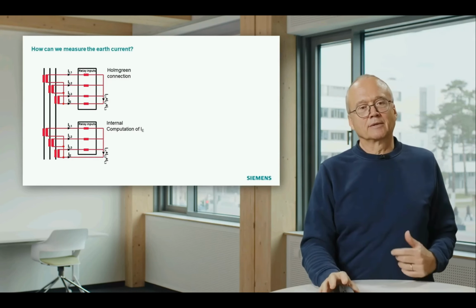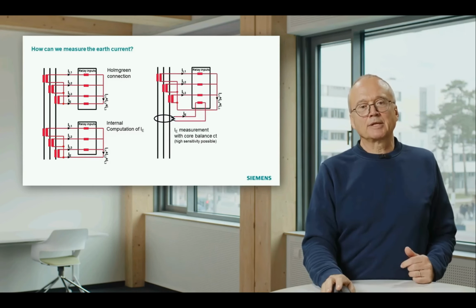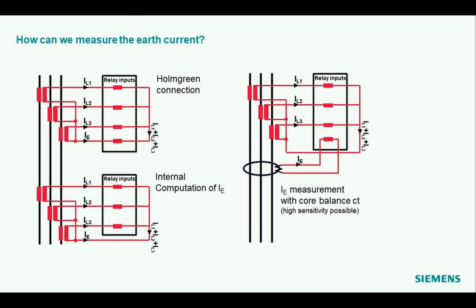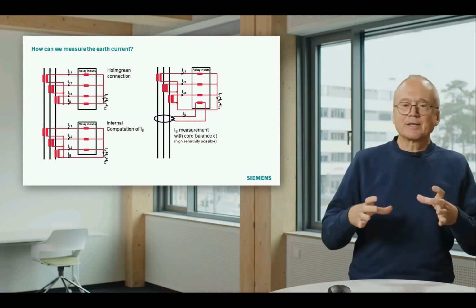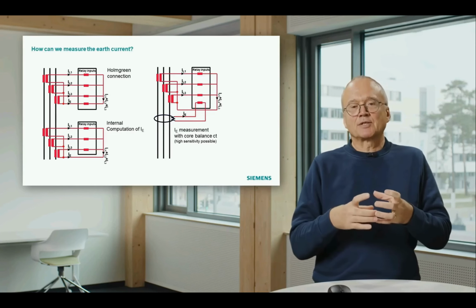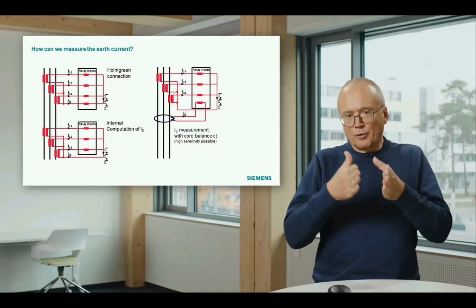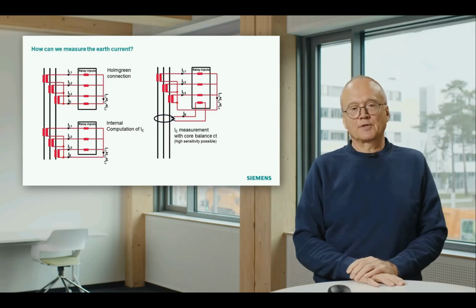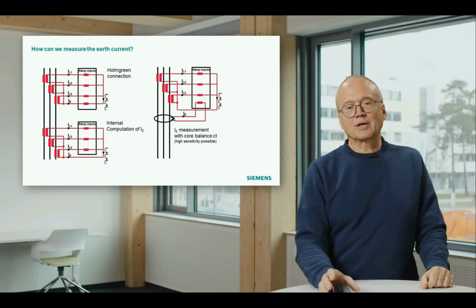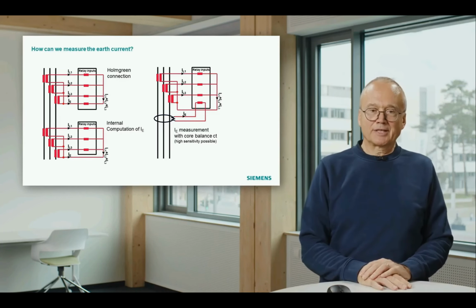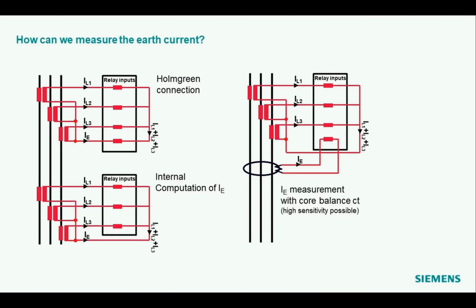If you want to be more sensitive, there is a possibility, and that is indicated here in this diagram. Then we use a separate CT that is called core balance CT, and that is a CT which physically measures the current of the three phases. That means all three conductors go through the core of this current transformer, and with this installation you can get much more sensitive measurements, and for that reason there are also sensitive measurement inputs available in the relay. So that was the question, how can we measure the earth current?